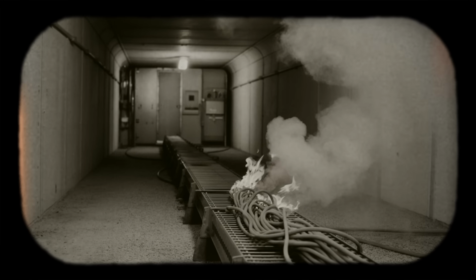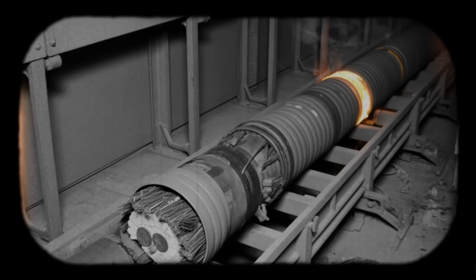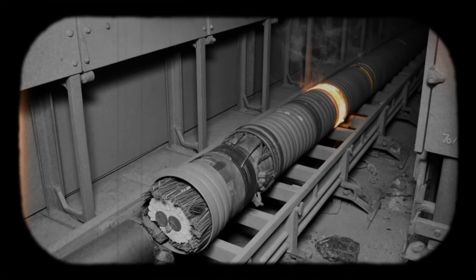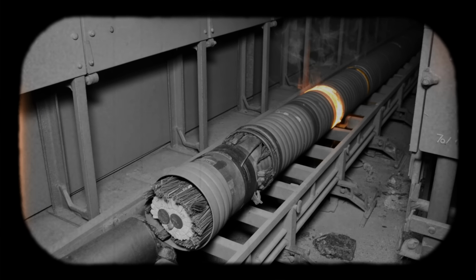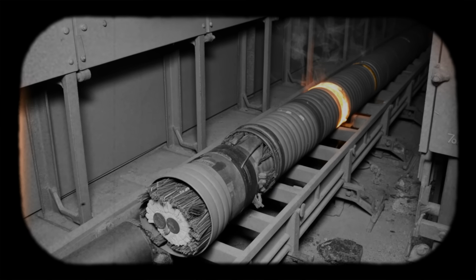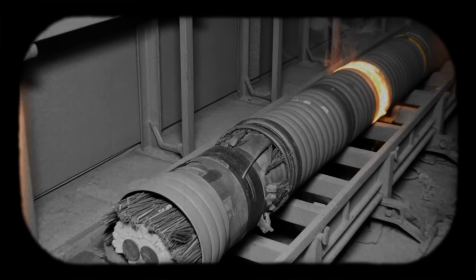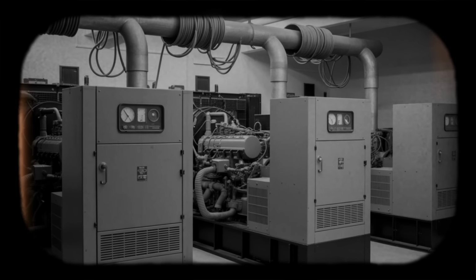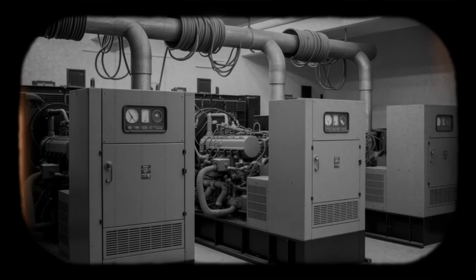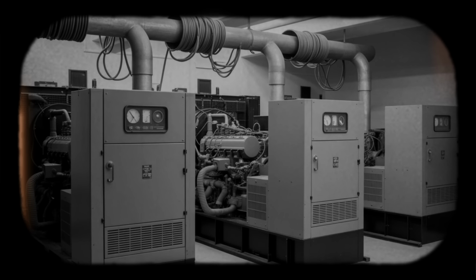The OECD Nuclear Energy Agency's reconstruction noted the sequence precisely. The fire was ignited by a short circuit on a 6 kV cable that lasted for about 7.5 minutes and overheated the cable over a distance of about 120 m. The lack of selective protection and fusing on the 6 kV side, a feature that might have isolated the fault more quickly, allowed the current to persist.